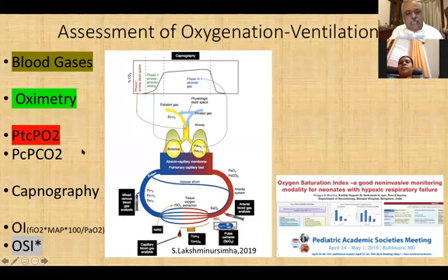They basically have a heated electrode through which you can get continuous monitoring. The only problem is the electrode tends to burn the skin and you need to keep changing the electrodes, and it's very expensive to change those electrodes as well. What many of us in the NICUs are also using is capillary blood gases. Capillary arterialized properly from the periphery like a heel prick, properly taken with a lancet in an anaerobic environment without oxygen contamination, is a very good reliable thing for the pH and PaCO2.